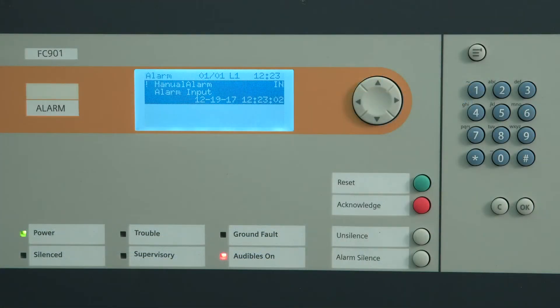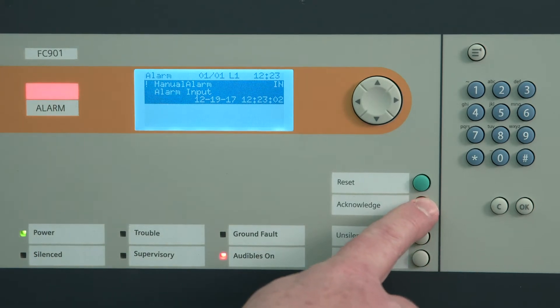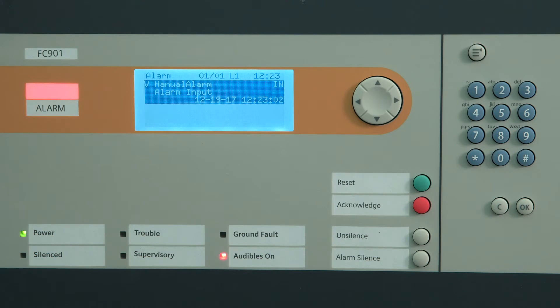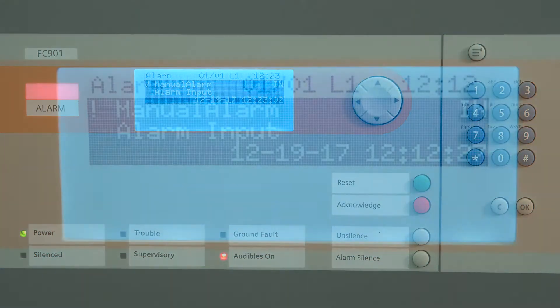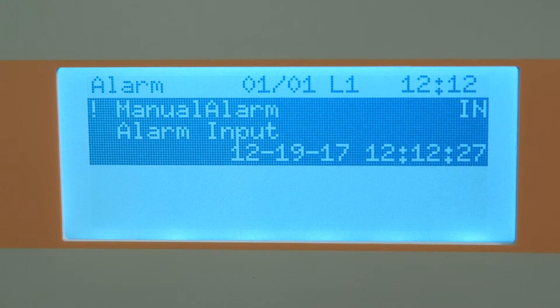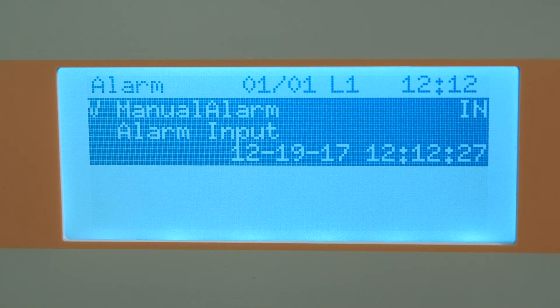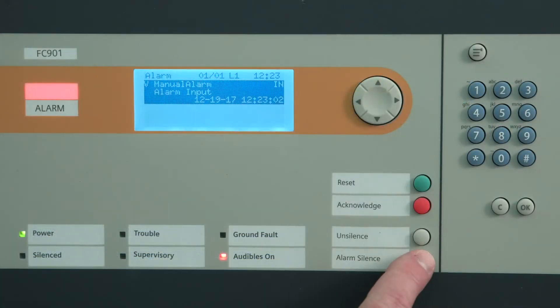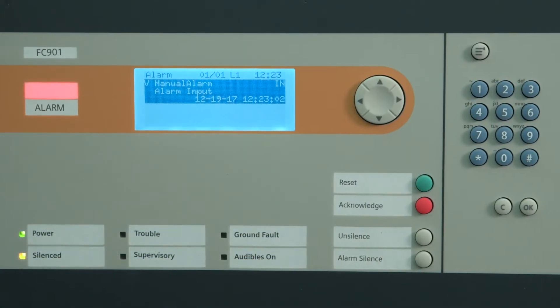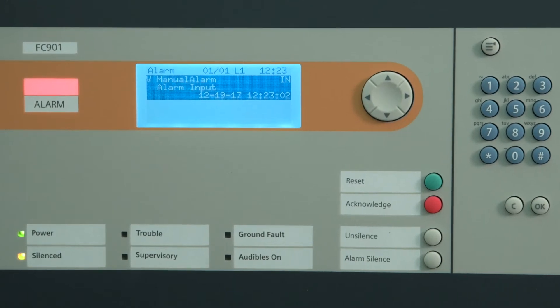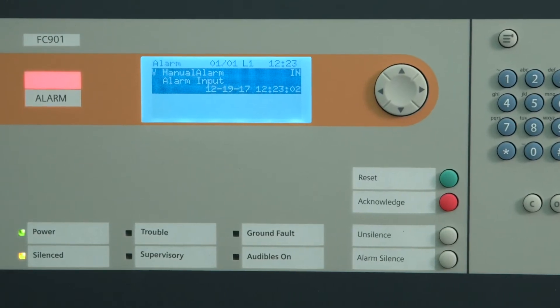We're going to step through several typical events on how to operate your panel, but keep in mind that only authorized personnel are allowed to access system controls. To acknowledge the alarm, press the acknowledge button. The local buzzer will be silenced, and the alarm LED will change from flashing to on steady. As you acknowledge an event, the exclamation mark changes to a V to the left of the description. To silence the notification appliances after evacuation, where permitted, press the alarm silence button. The notification appliances will be silenced, and the LED indications will change from flashing to continuous.